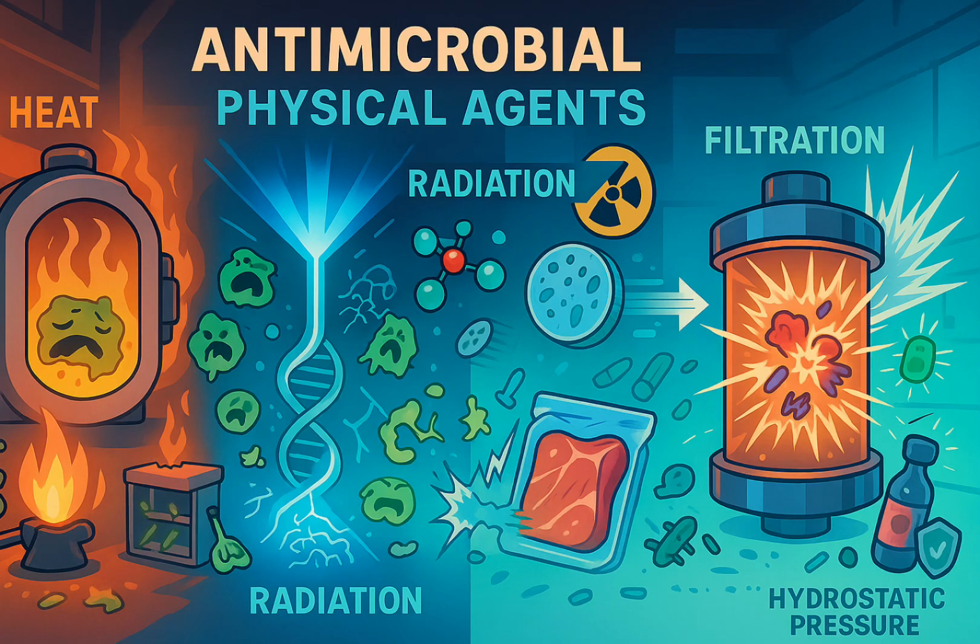That feels like a crucial detail often overlooked. And the sources have some really eye-opening data on how the volume of liquid you're sterilizing dramatically impacts the time needed. Absolutely. It's not just the 15-minute holding time. That time only starts after the center of your material actually reaches 121 degrees C. Right. For small volumes, maybe up to 50 milliliters, heat transfer is quick. But the larger the volume, the slower it is for the center to heat up. Gotcha.